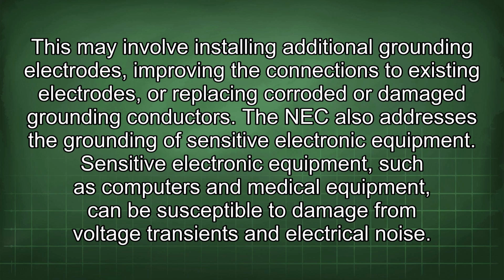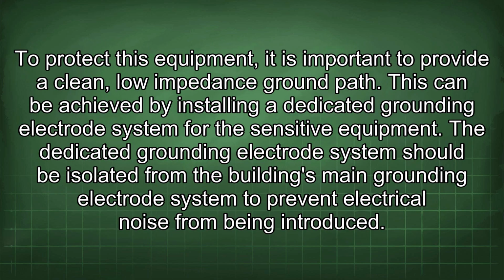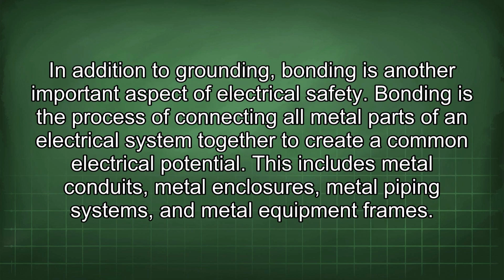The NEC also addresses the grounding of sensitive electronic equipment. Sensitive electronic equipment, such as computers and medical equipment, can be susceptible to damage from voltage transients and electrical noise. To protect this equipment, it is important to provide a clean, low-impedance ground path. This can be achieved by installing a dedicated grounding electrode system for the sensitive equipment. The dedicated grounding electrode system should be isolated from the building's main grounding electrode system to prevent electrical noise from being introduced.